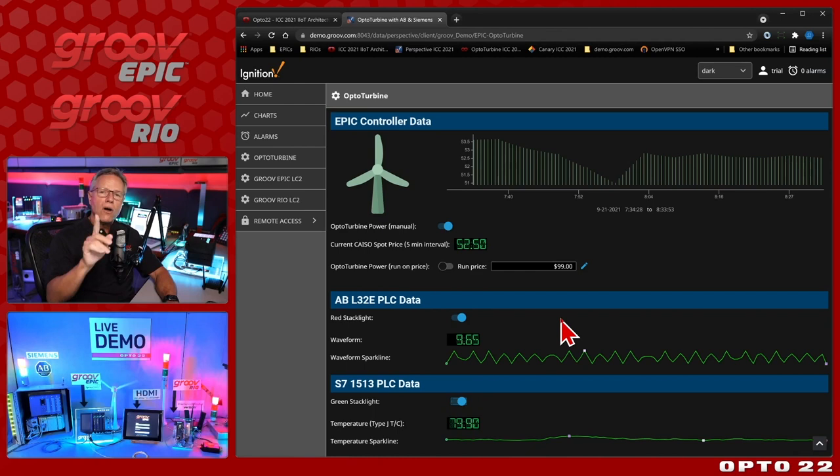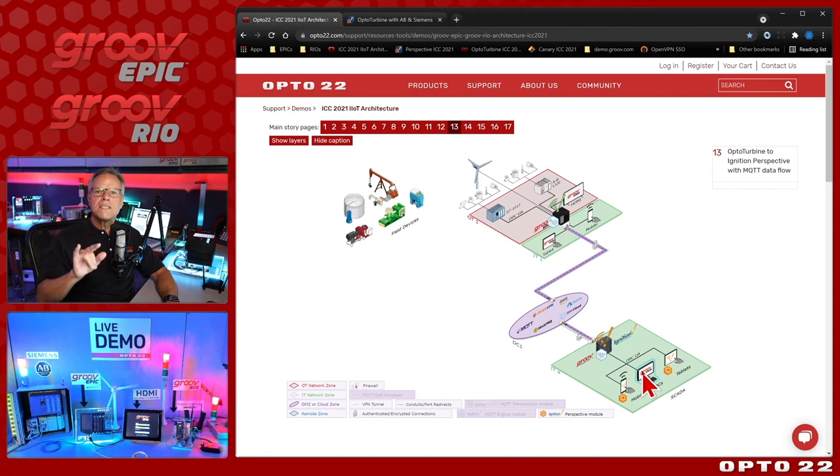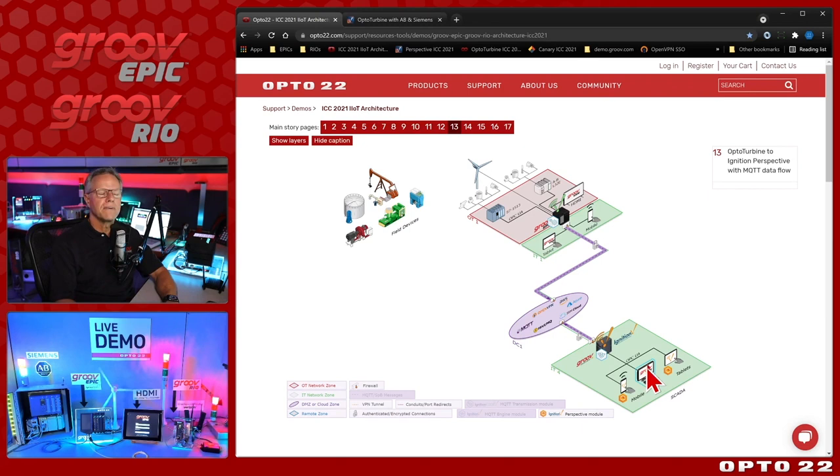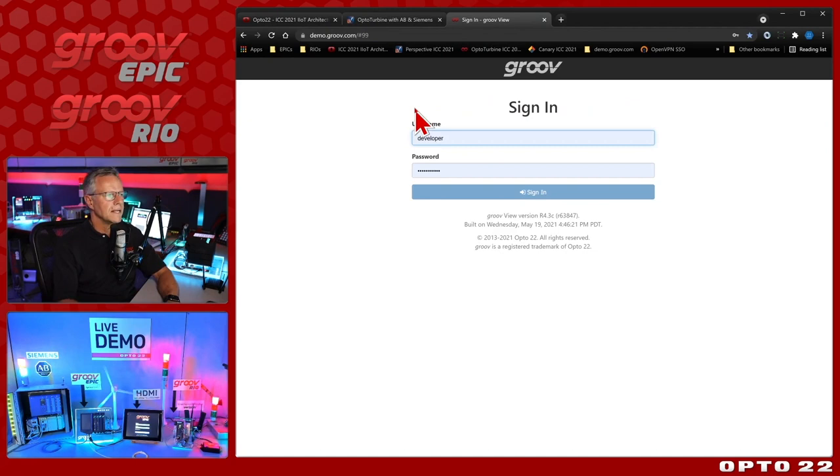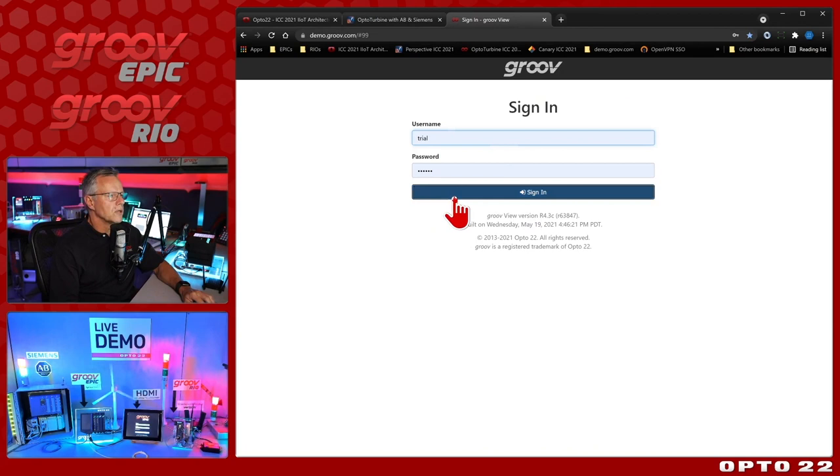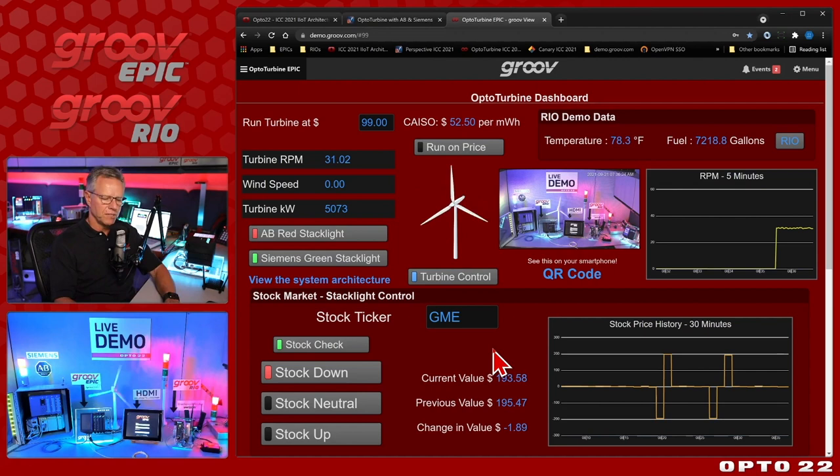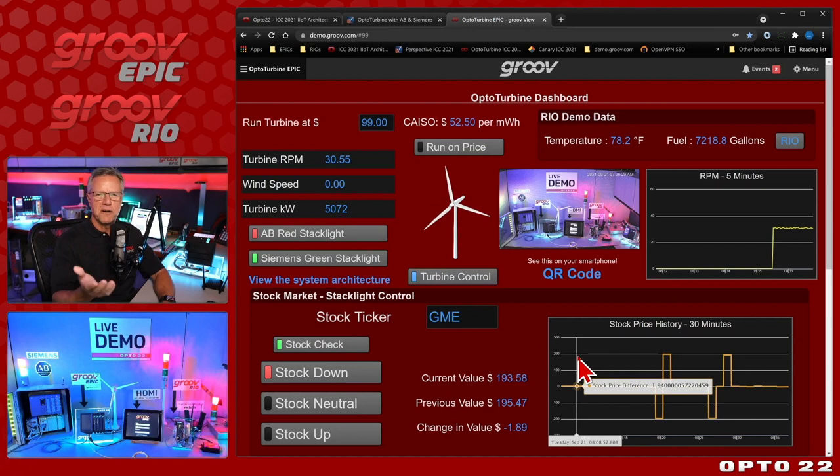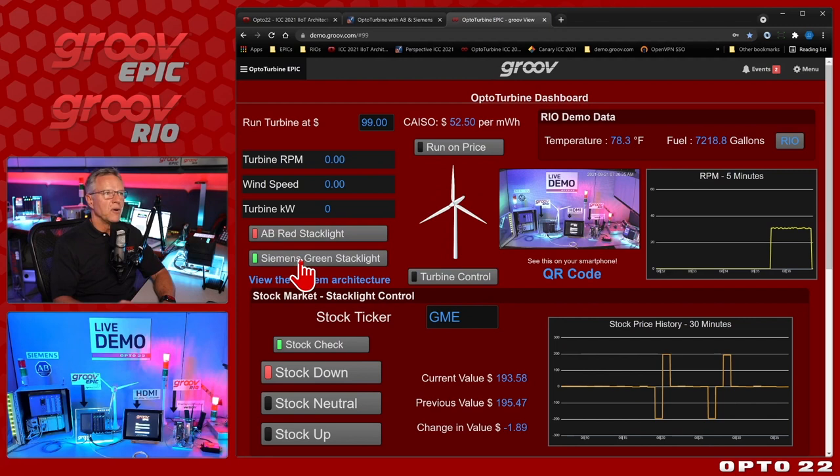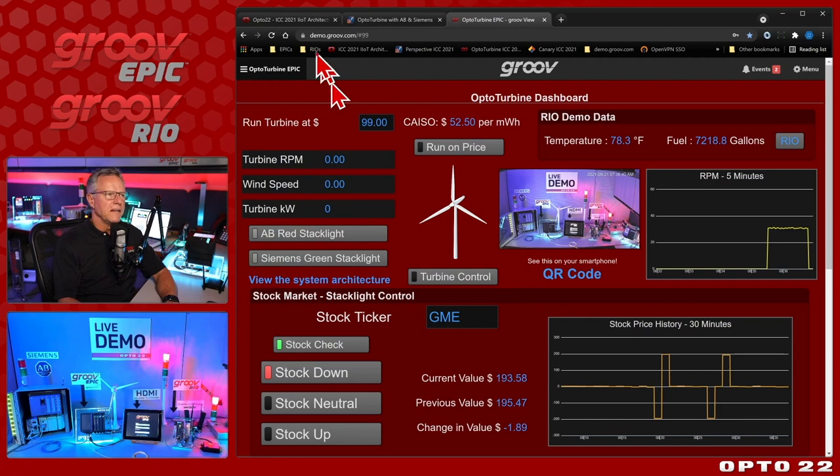Now I also mentioned I could actually see some of this data on an OPC UA client, some third party client. So even though I'm using MQTT, I can still take advantage of my existing software. I'm going to open up an OPC UA client and log in there as well. This is an OPC UA client but taking advantage of all of that MQTT and cyber secure environment. Here we'll turn off the PLC, turn off the turbine, and turn off the PLC stack lights as well. As you can see, works just as well as it did with the perspective, but we're just using OPC.